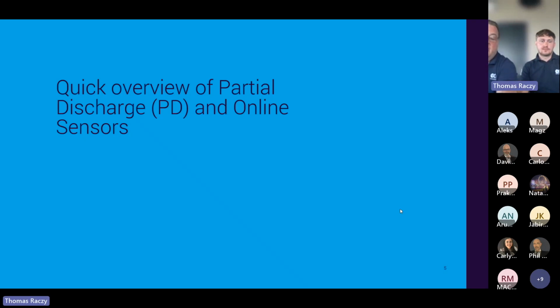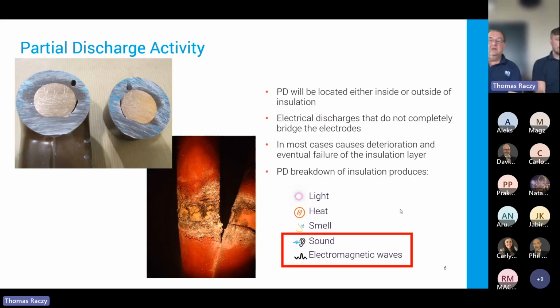Quick overview, some photographs of partial discharge. I think most people have seen these before, but it's just to give people some of the instances of what can cause partial discharge. It can be located either inside or outside the equipment. The picture on the top left-hand side shows voids, which would eventually build up into heat and also breakdown of the units. We've got all the usual signs of surface discharge, where it has tracked on the other one of the cables, but it's not been detected at an early enough stage to stop the deterioration it is leading to.